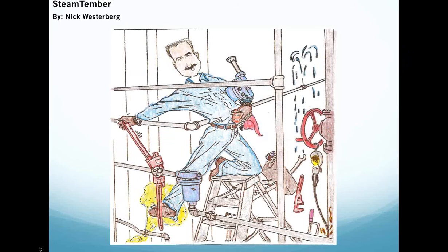Excellent. Well, everyone, SteamTember is that time when we get to fire the systems back up and get ready for the fall and the winter. Whether you're at a college, an institution, or an industrial processing facility, not everyone uses the full load that they're capable of producing in their boiler up until the time it starts cooling off. And one of my great examples is a local college. When the college kids come back and enter college here in the northern part of the United States, it starts cooling off and we start firing up the dorms. And boy, does it create a tremendous amount of opportunities inside the STEAM system for those of us in maintenance and in the STEAM world.